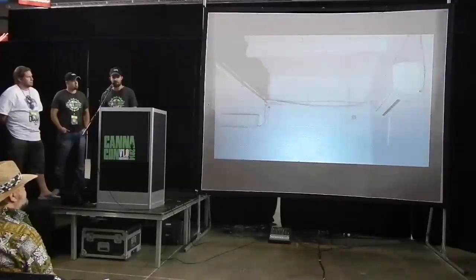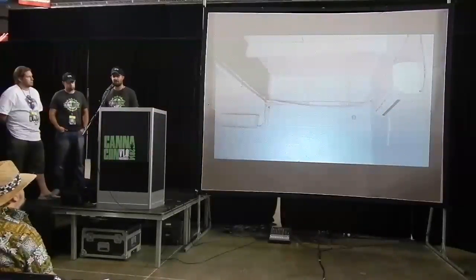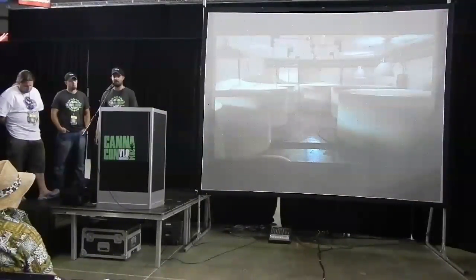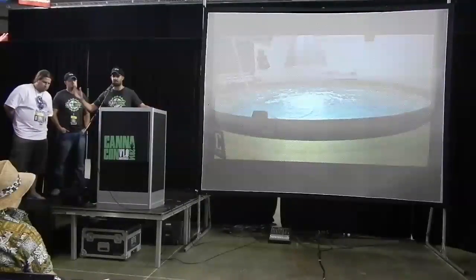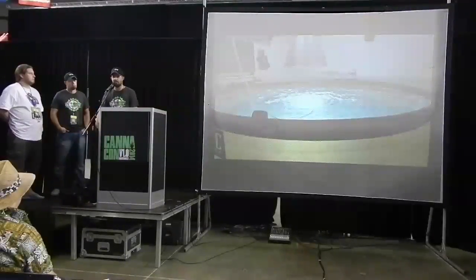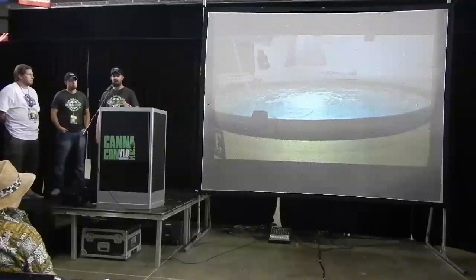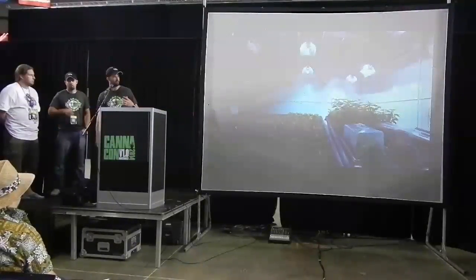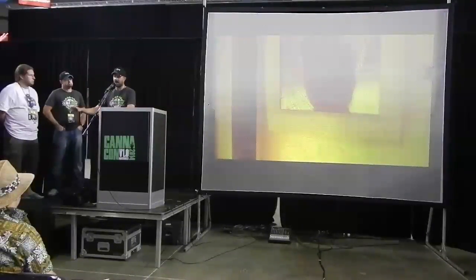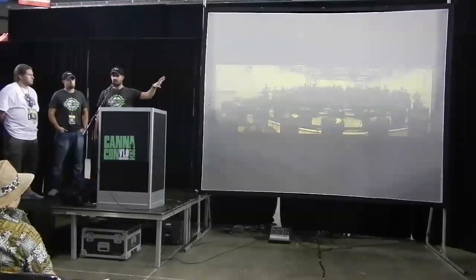Now, where we've been headed with 502 is with the package units and the ducted systems. We love the forced air systems from 502 because you can have a room with 25-foot ceilings, 30 feet across by 75 feet wide. It doesn't matter as long as you size the ducting appropriately for the room, not only the square footage, but also air distribution for getting the air into the middle room. The air coming out of a package unit is 10 times the CFM out of an air handler.